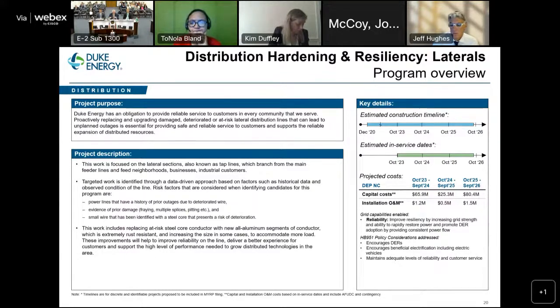This is a data-driven approach, looking at outage history and very specific cause codes for outages on those laterals, as well as a review of the physical condition of the wire—typically looking for damage or multiple splices indicating the line has failed before and been spliced back together.